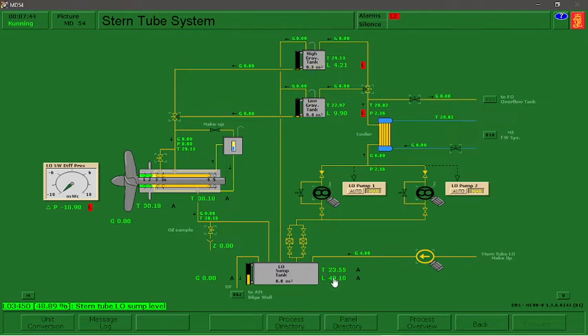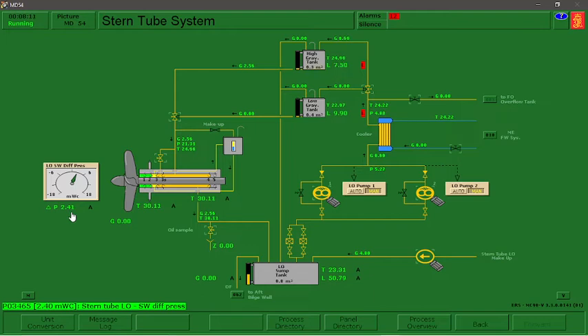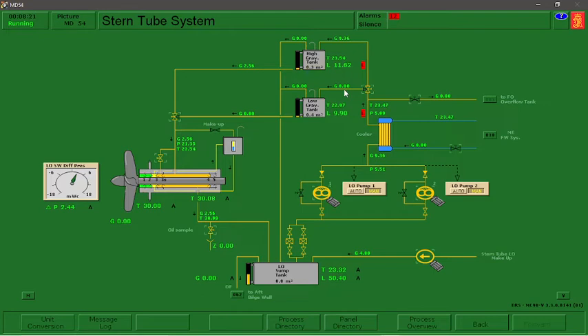We are now at 50%. Once it reaches 50%, do not close our makeup valve yet. Open the two gravity tank pumps and they will begin filling the high gravity tank. As you can see, our pressure is now reading normal. Just like the main tank, we need at least 50% level in both the high gravity tank and the low gravity tank.